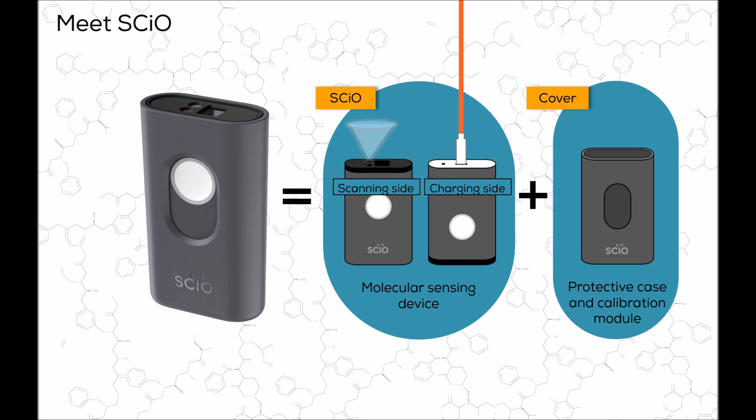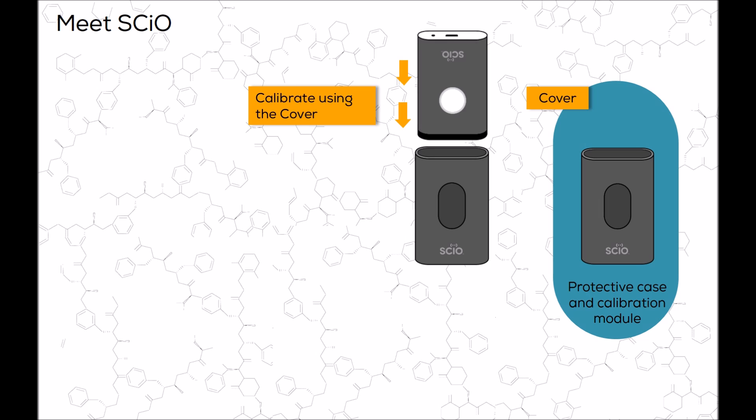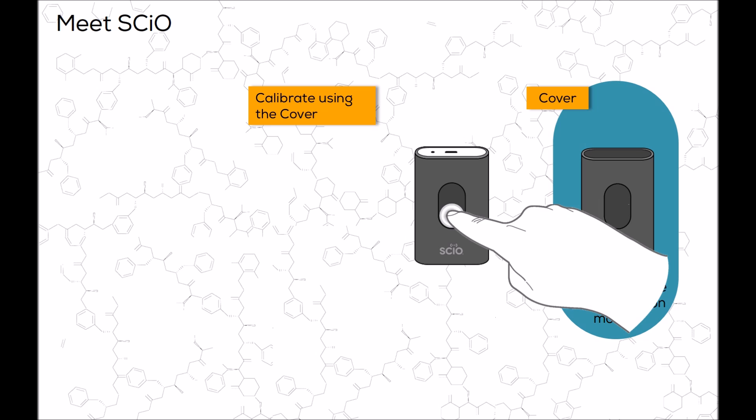The SCiO Cover is both protective and functional. Your SCiO requires occasional calibration and the calibration device is located within your SCiO Cover. To calibrate SCiO, place your SCiO with the optical head down into the cover and click the function button or tap Calibrate in the app.